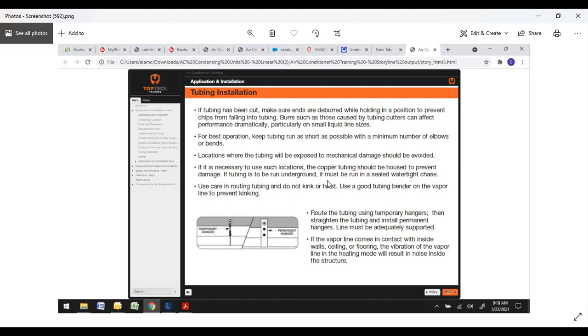If the tubing is to be run underground, it must be run in a sealed, watertight chase. Use care in routing tubing. Do not kink or twist. 3/8 is easy to bend. 5/8 so-so. 3/4 and up, unless you're really, really good, you'll probably kink it. I always do. So if you're going to have to do any major bends, if you have a good tubing bender, that works wonders. It looks good, and that's one less braze joint or connection you have to make that can go bad. So it's always a good idea to use a tubing bender. And if you do kink it, don't leave it in there. Cut it out and start over.